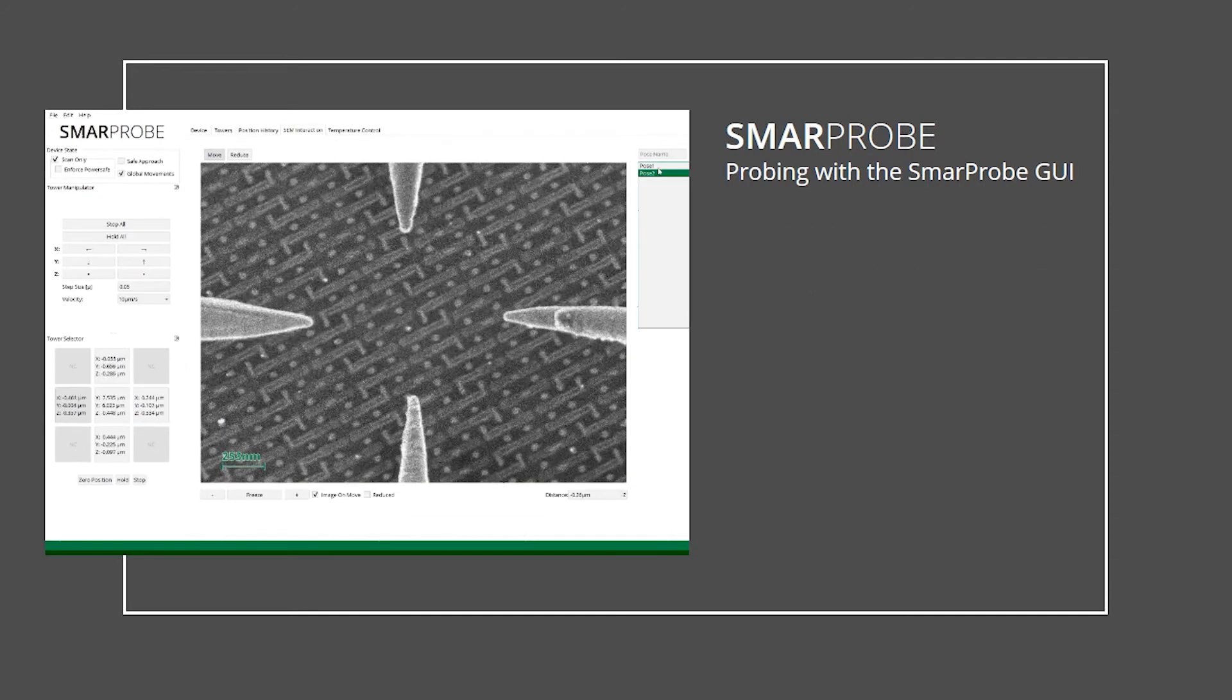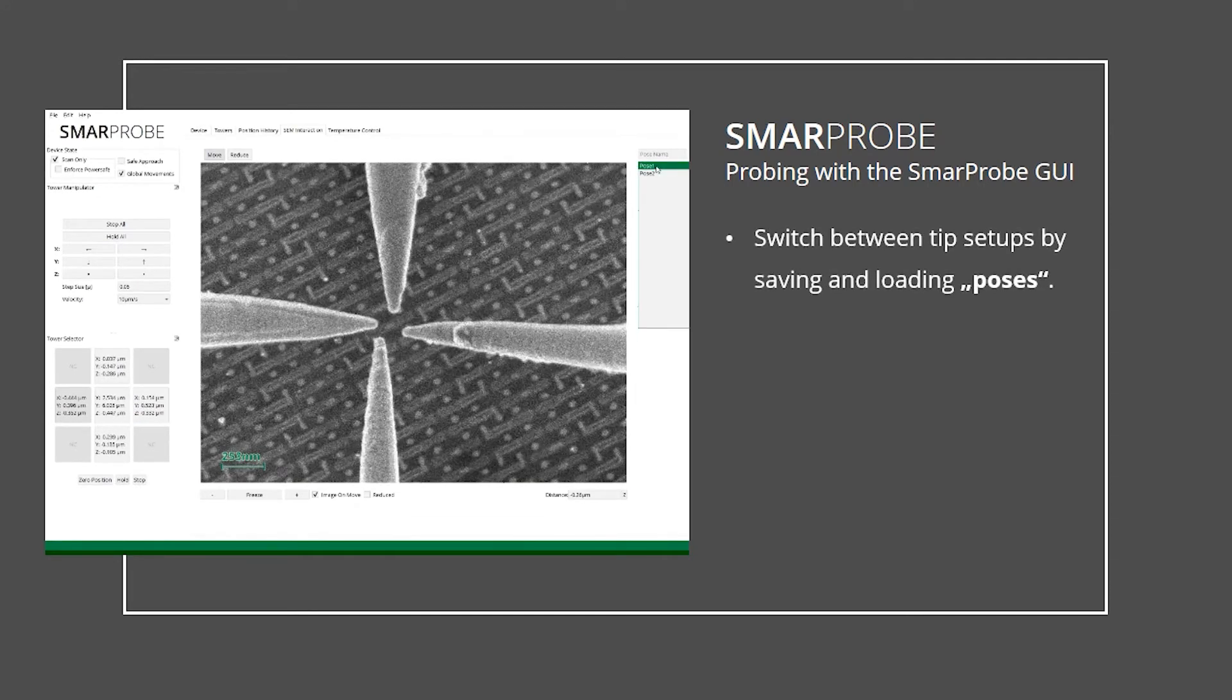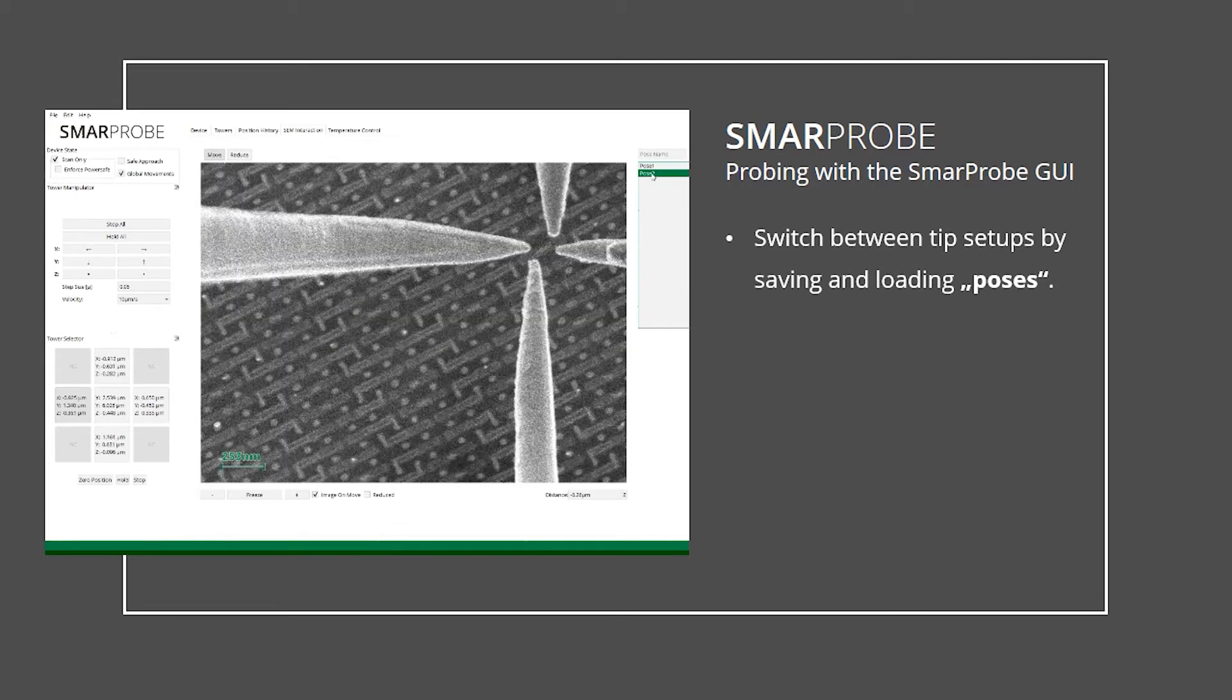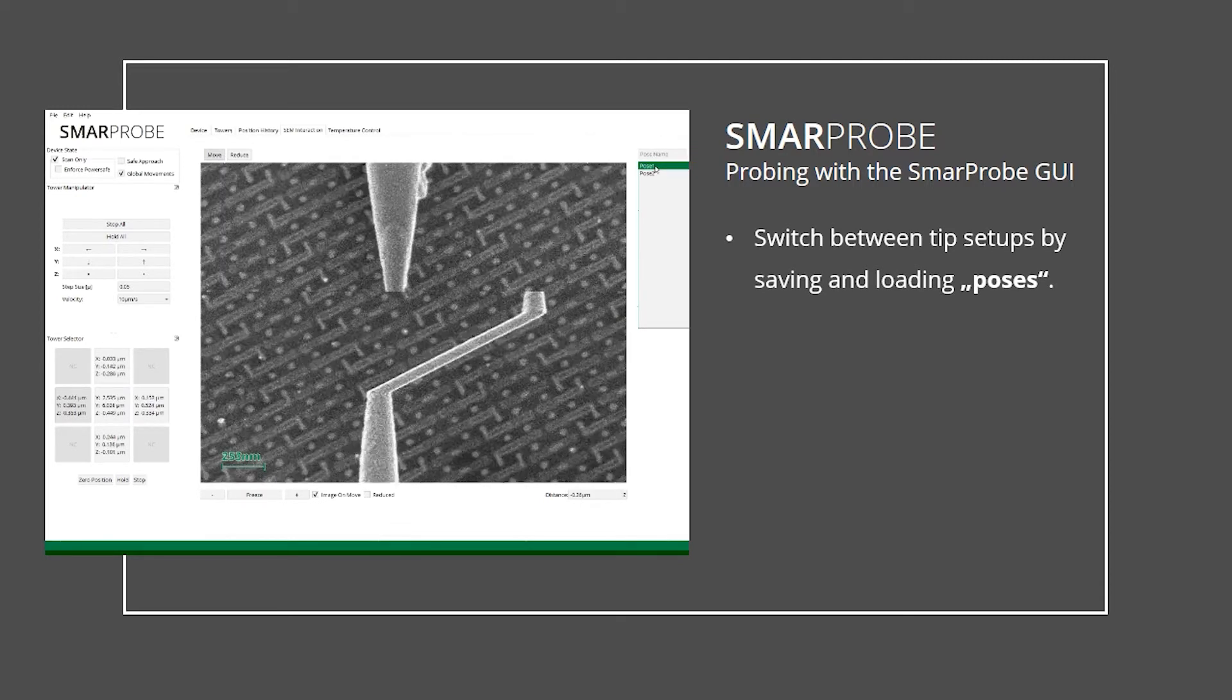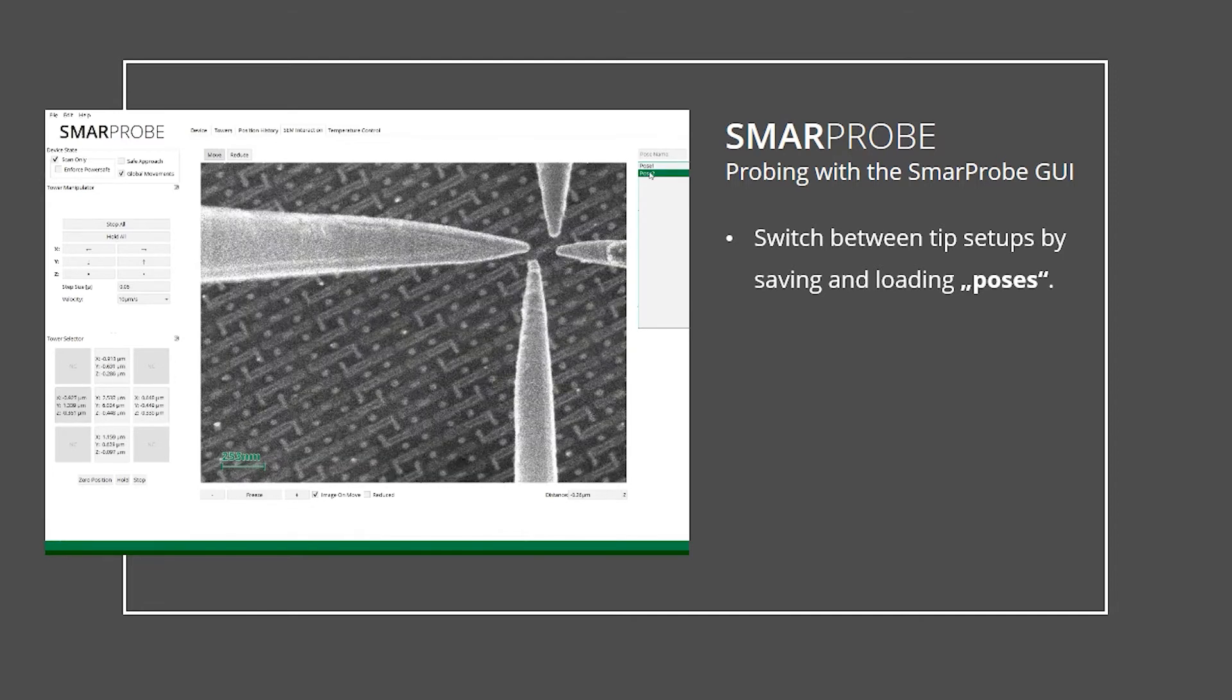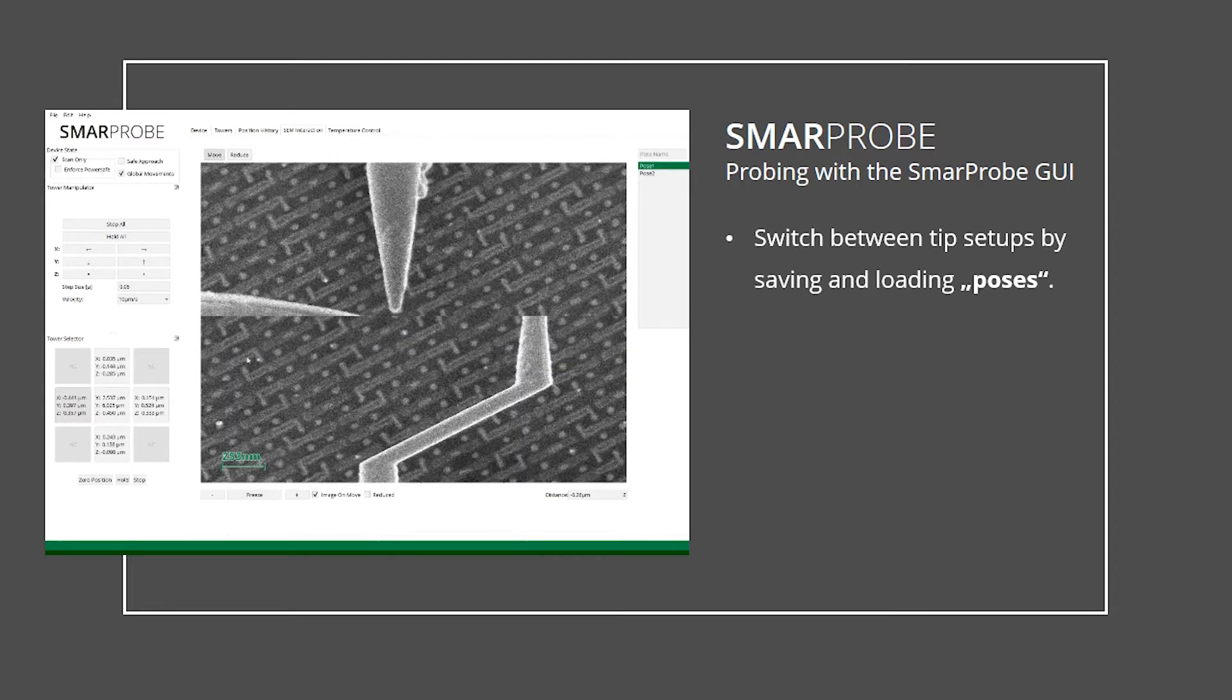By saving a specific composition of manipulators and sample stage into a pose, it is possible to switch from one test structure to any prior contacted test structure by loading that specific pose.